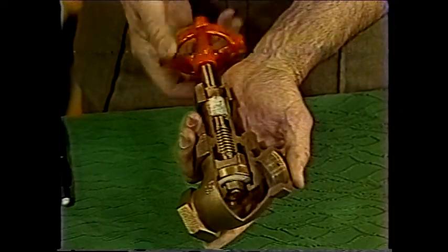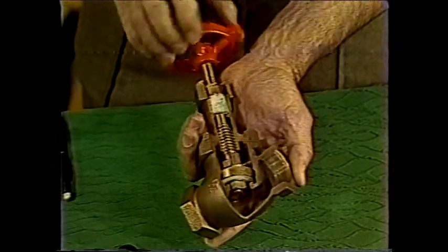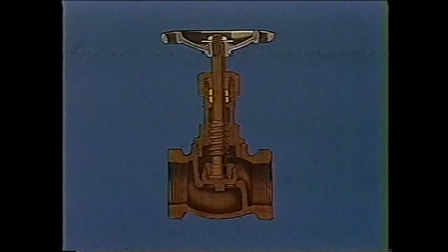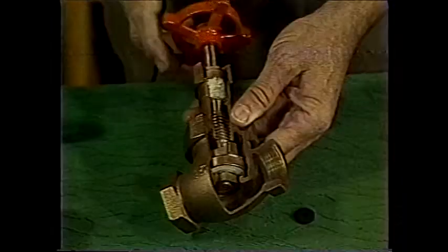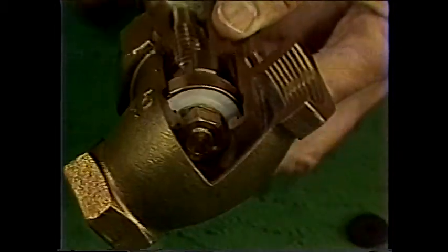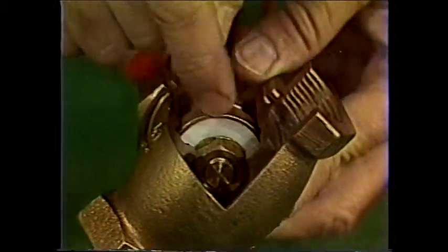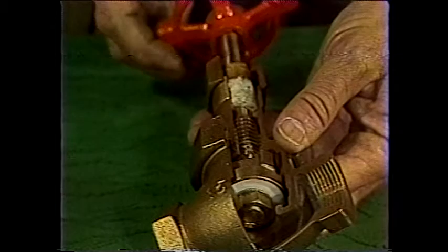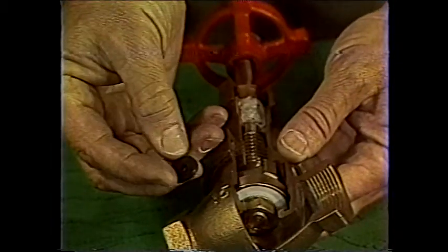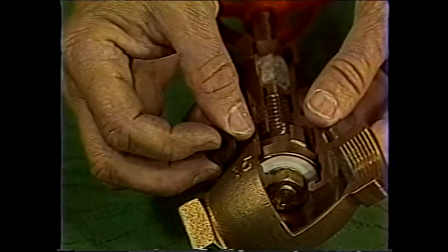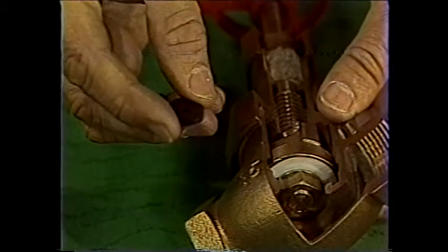Next, let's discuss globe valves. Globe valves are quite common and are widely used for throttling applications. They're built like this, with a circular disc which closes against the seat right here. The seat is normally ground metal, while the disc may be ground metal or any of several non-metallic materials. The non-metallic discs are replaceable, which is an advantage since many throttling applications tend to cut them out. Most faucets around the home are a type of replaceable disc globe valve. This is a disc, or faucet washer as it's called, right here.